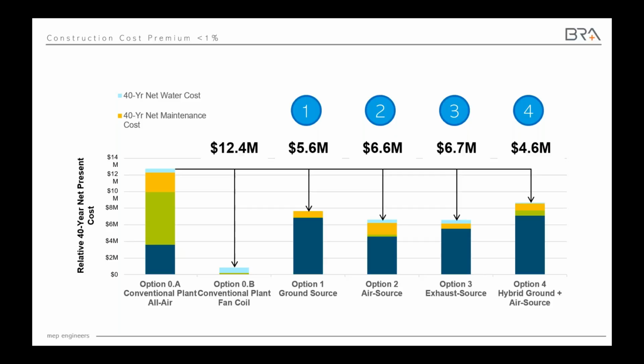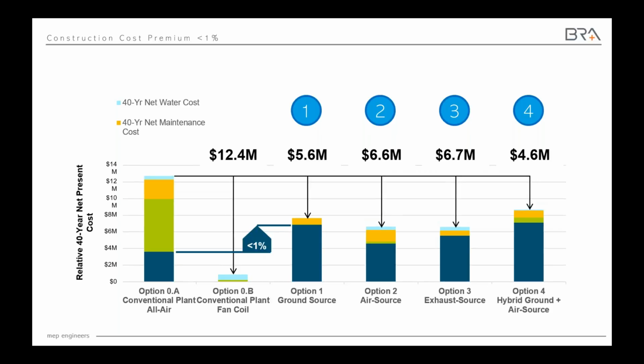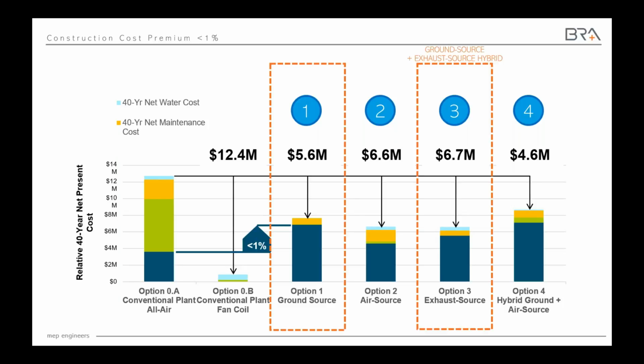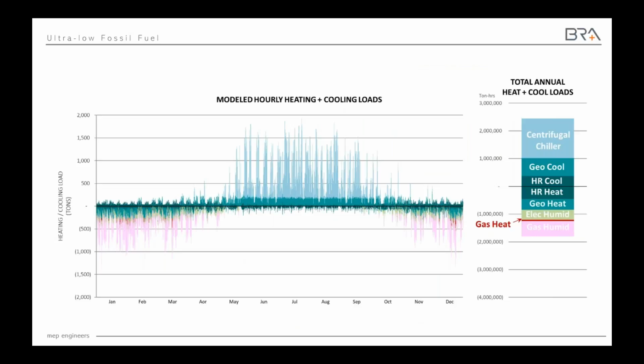You can see though on the next slide, even those more advanced options are below a 1% construction cost premium compared to the conventional design. And on the next slide, you can see ultimately Alexandria selected a hybrid between the ground source, which they had committed to the city of Cambridge to include in the design, and this advanced exhaust source heat pump system. What that means is as the building operates, you're really using the heat recovery and the geothermal system to slash your building heating from fossil fuels.